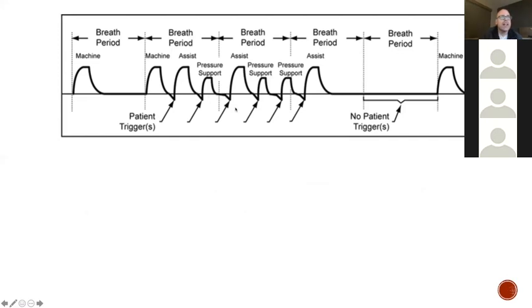Then they tried to take another breath here. It's into a new breath cycle, so it gave them that full breath. Then they took a couple extra little ones here. They were just supported with pressure support. Then they took another one. They got a fully assisted breath. You can see down here, the next breath cycle, they didn't trigger a breath, but it didn't give them one because they're already one ahead for the minute from back here.